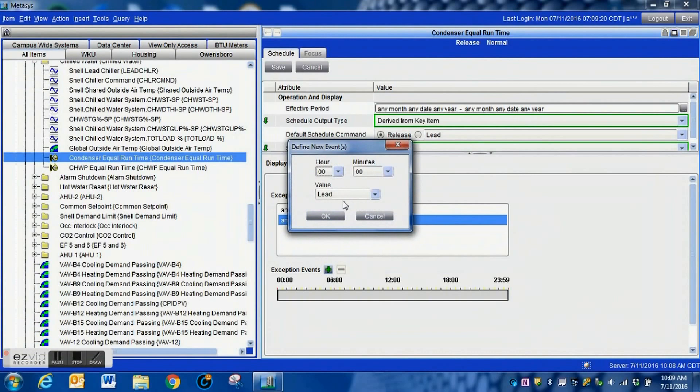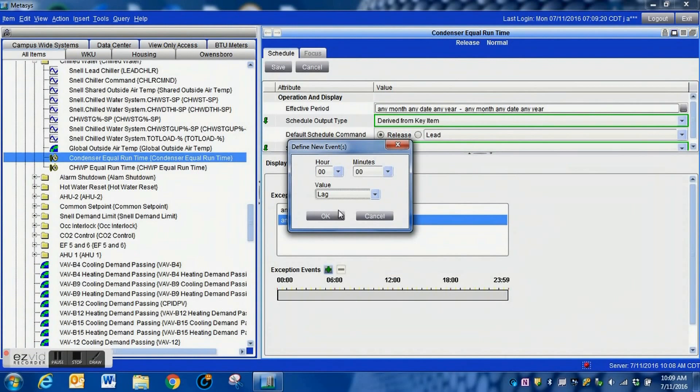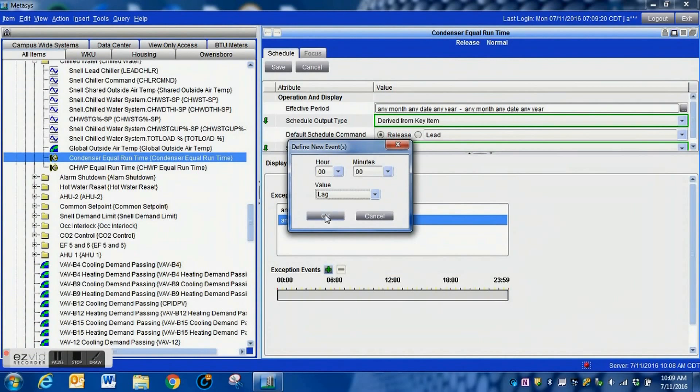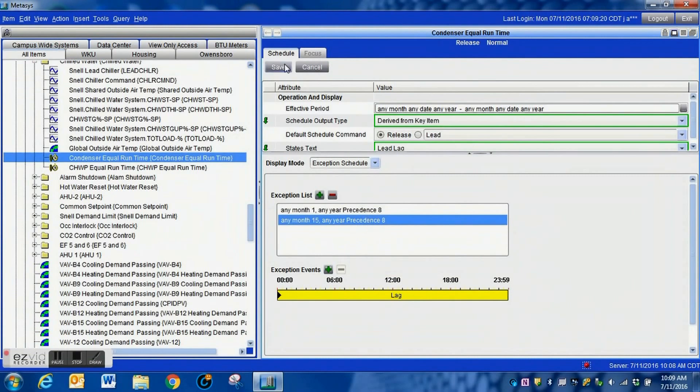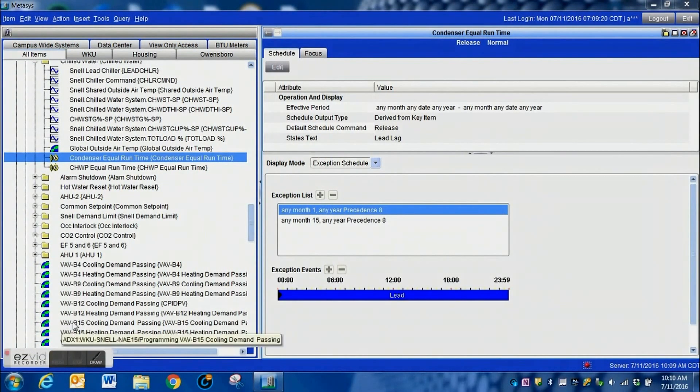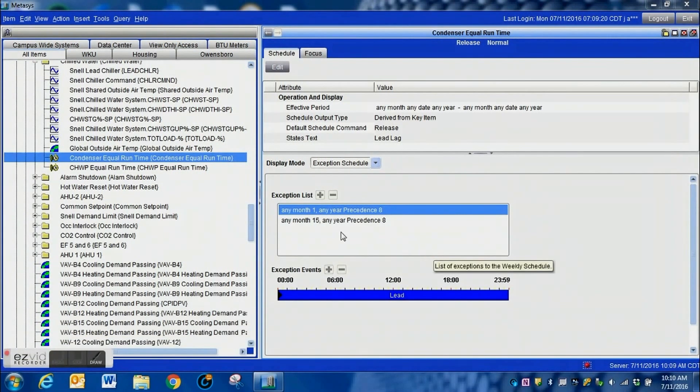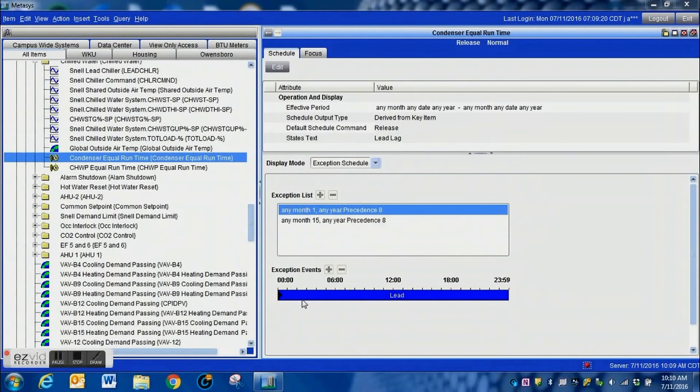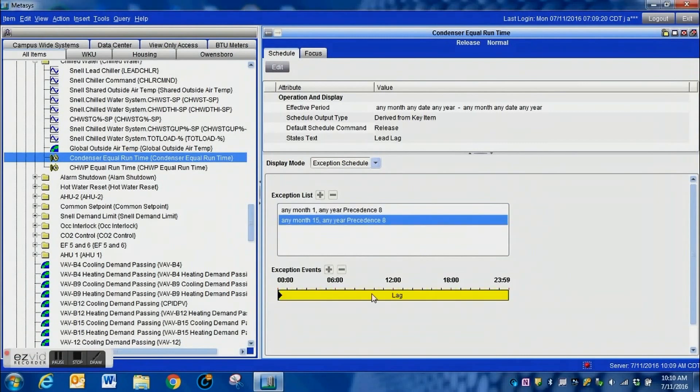And we hit OK there. Now on the 15th of the month what we will do, we hit our plus sign to add this in, we switch that to lag and we hit OK. And that way on the 15th of every month it will switch to the lag pump. Here's first, it goes to lead the first of every month and then on the 15th back to lag. It's a very simple way of doing it, rotating these pumps twice a month.